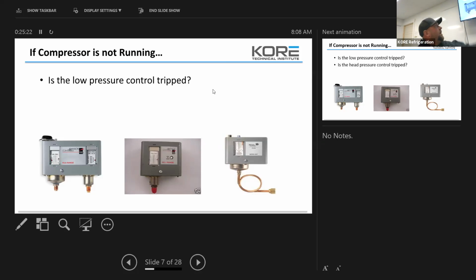And then, you may have a fan cycling control on your condenser fan. All those types of switches look the same, so you could have 2 of these boxes. There's also an oil fail control, the old mechanical ones. It'll have 2 cap tubes, one going into the crankcase and one going into the oil pump, looking for the differential of pressure. So the first thing you need to identify is what safety controls you have on your compressor, and then you need to start troubleshooting through those controls to see if you have an open switch that's breaking the power to your compressor contactor.